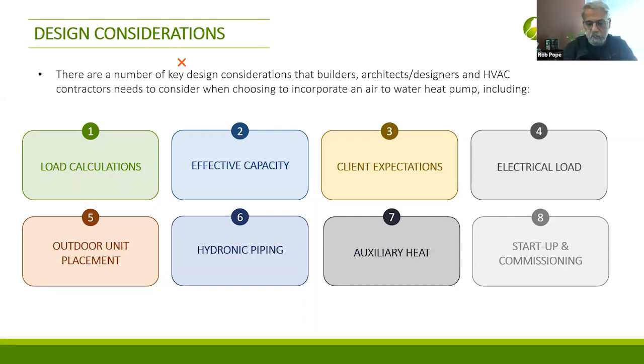And of course, you need to document all that. One, for the manufacturer - if there are any warranty issues, you'll need the documentation from the commissioning. Secondly, you want to establish your baseline: we install the system, here's where all the numbers are, pressures and all that kind of stuff, so that down the road future technicians can see where the baseline is and where we're at now.